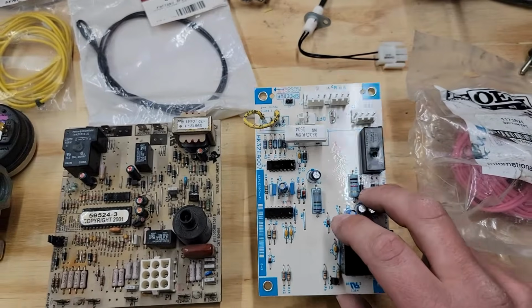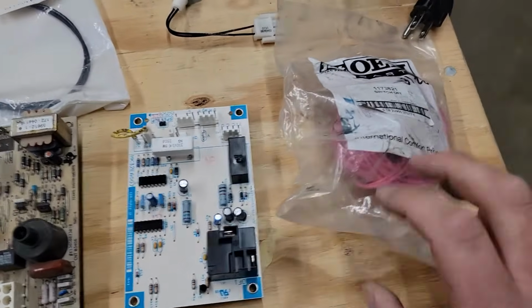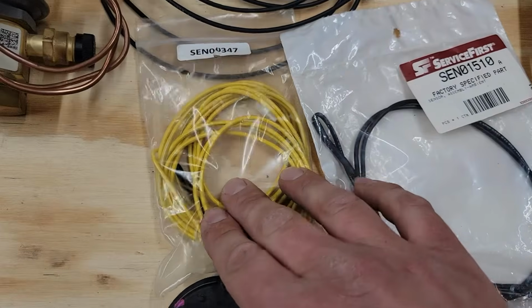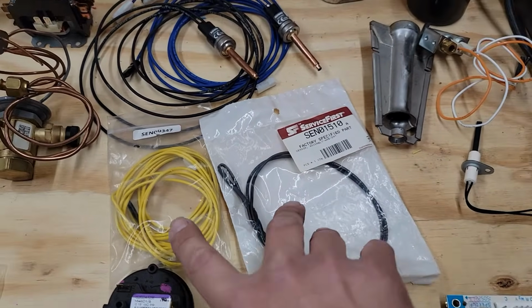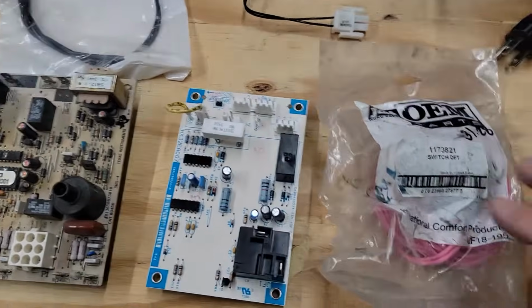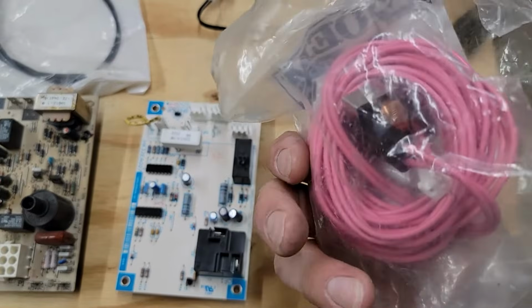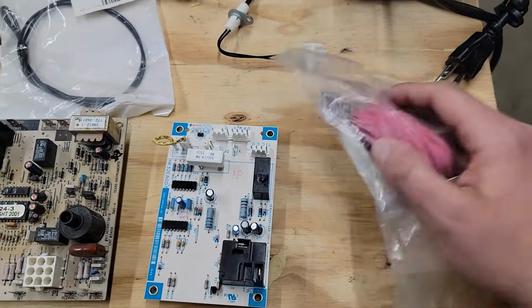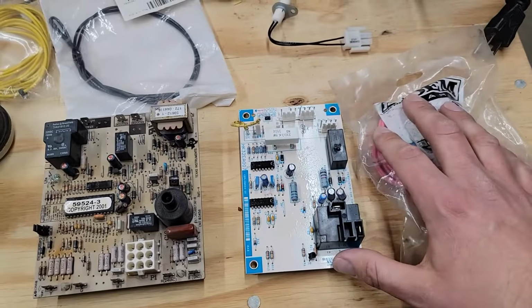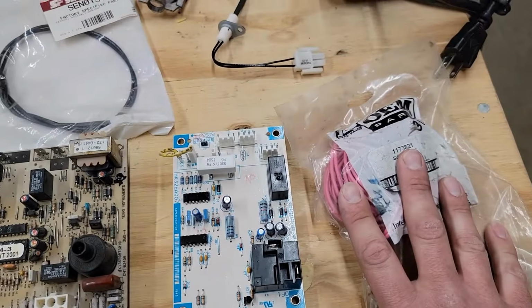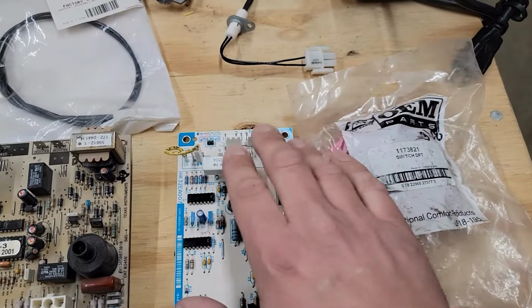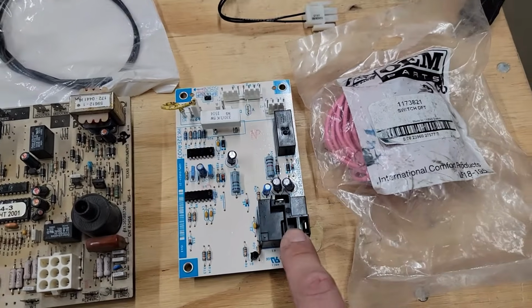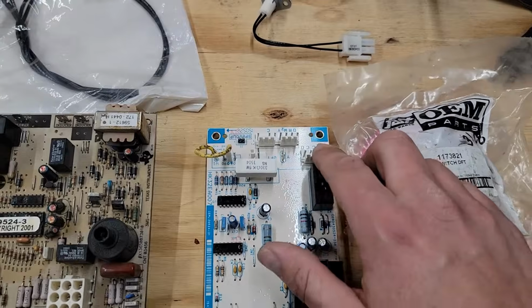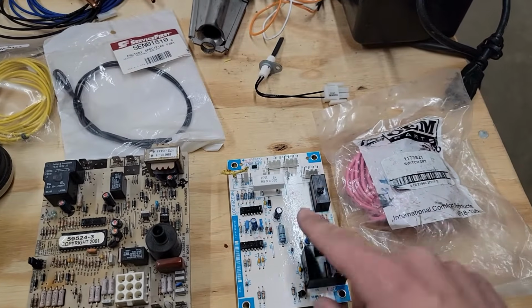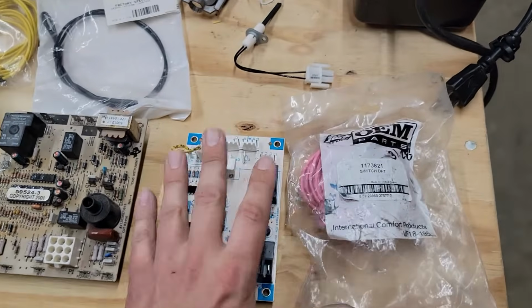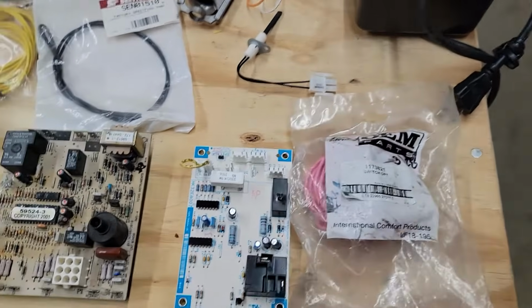And then this right here is a defrost board. Okay, this defrost board usually has time and temperature. Some have sensors like this, an ambient sensor and a coil sensor, and usually defrost depends on the delta T between these two sensors and then time. Or you have a defrost switch, okay? This is a switch right here that's mounted on the outdoor coil, and when this switch opens and closes, then that changes the defrost. So this board has a relay that goes to the outdoor fan, and during defrost, whenever this switch opens and closes, that engages this board to open the relay for the fan, it shuts the fan off, and then it energizes the cooling so that the compressor is running and cooling, the reversing valve switches, and sends hot gas to the outdoor coil. So that's kind of a little bit of an overview of the defrost board and then this defrost switch.